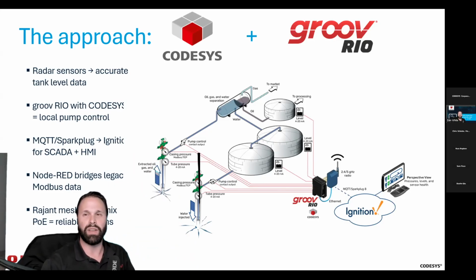Along with that, they've got Modbus signals that feed into the groov RIO, as well as the groov RIO's edge I/O. Each groov RIO, running its own CODESYS platform, now acts not just as a data collector. You've got a controller, automatic pump control, and all the tank monitoring without having to wait for anybody at the SCADA site, all controlled and run locally at the edge.